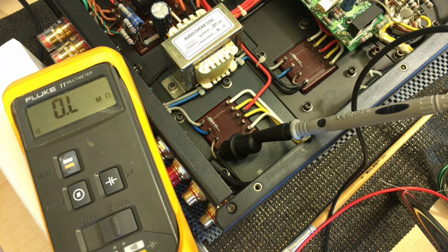So the thing to do is take the transformer out and see if it's potted. If it's potted, there's nothing we can do, unfortunately. If it's not potted and it's something accessible and visible, we could clean it up, insulate it properly, and remove that path to ground.